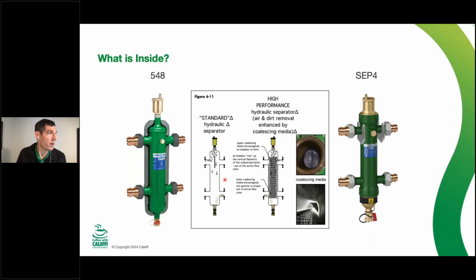So this will still work as a primary, secondary device, but when you get to a high performance device, the way that I would describe that in generic terms, we have to have some sort of coalescing media inside there, and different manufacturers do this with different materials. We have to have something in there that helps facilitate the separation of air and dirt. So some sort of coalescing media that I'll go into more detail with when I get to that section. That's the difference between standard and high performance. So again, if this is the 3-to-1 ratio, both will absolutely work for primary, secondary piping, but it's going to take you longer to get air out of this system, and you may have some dirt go right through and get back into a heat exchanger somewhere else if you are using a standard versus a high performance. So not all interiors of these devices are decorated the same, I guess, and that's what moves to a premium capacity separator. And this one also has magnetic separation, which I'll get into more as well.